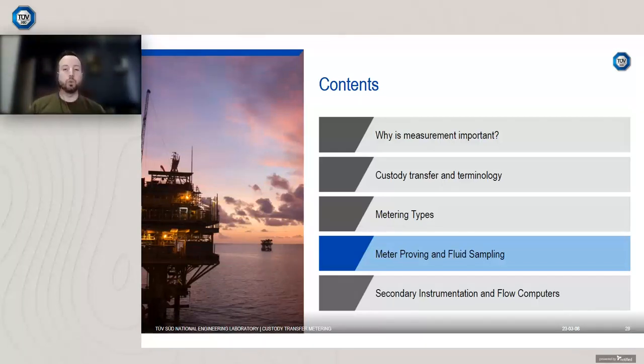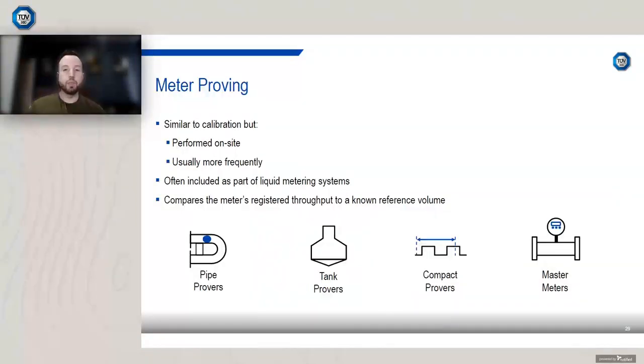So I'm now going to move on to meter proving and fluid sampling. So these are again quite important activities when it comes to custody transfer metering. So obviously, if you've selected a meter and you're using it to meter your flow, that's fair enough. But how do you verify the performance of the device? Well, obviously you can calibrate it at a laboratory, but that requires removing the meter, and in some cases that's not practical or achievable. So that's where meter proving comes into the fold, and it's similar to calibration, but it's usually performed on site and usually more frequently. So it is essentially a calibration, but it's usually done on site.